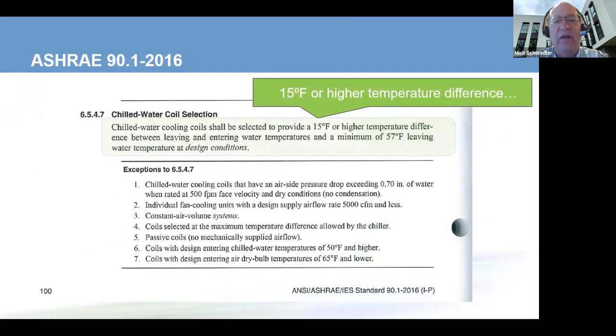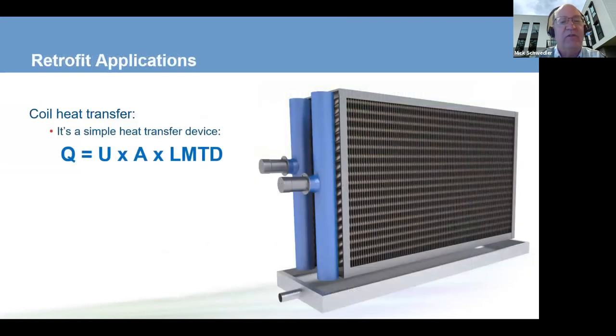That's one of the reasons ASHRAE Standard 90.1 2016 started to require you to select coils with at least a 15 degree temperature difference. Now there are exceptions. We're not gonna go through those today, but on our air handlers, at least a 15 degree temperature difference with a minimum 57 degree return water temperature. So our new selection parameters should be in the range of 57 to 42 rather than where they've been in the past. So from a coil heat transfer standpoint, it just transfers heat using that LMTD, log mean temperature difference.